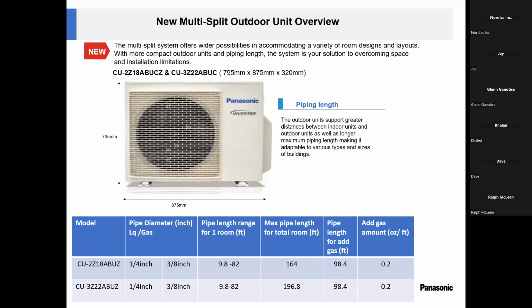The copper pipe sizes are the same, 3/8 and 1/4 inch. Maximum pipe length for the 2-zone is 164. Keep in mind the unit is only charged for 98.4 feet. And then after 98.4 feet, you need to add 0.2 ounces every foot.